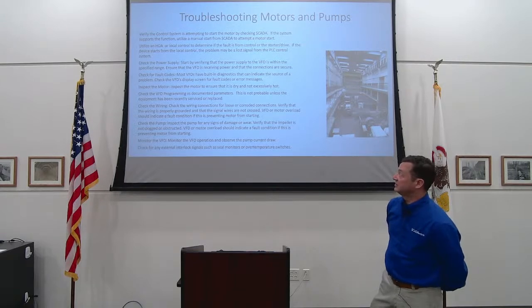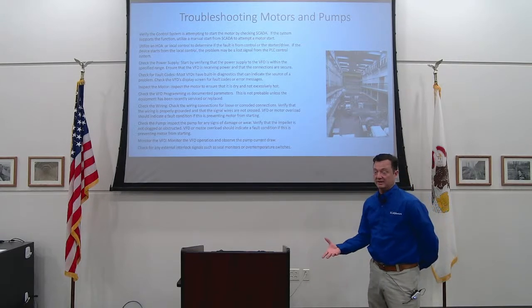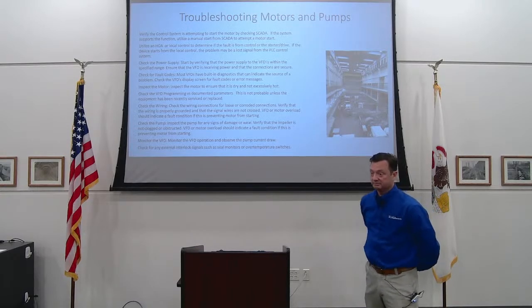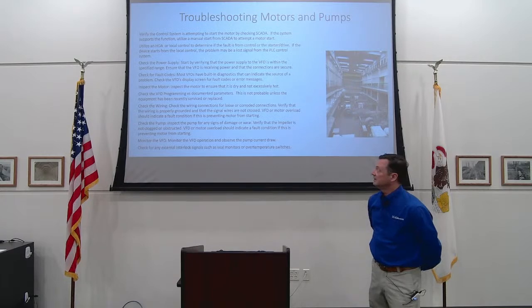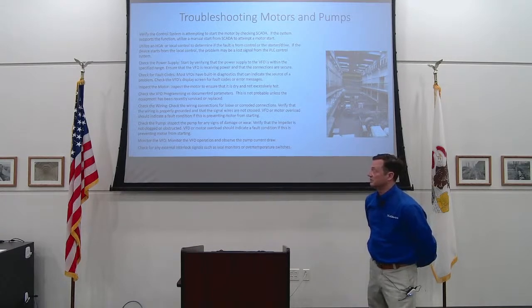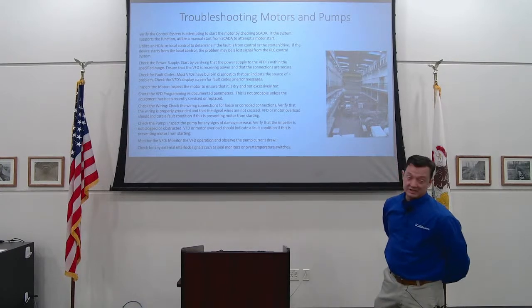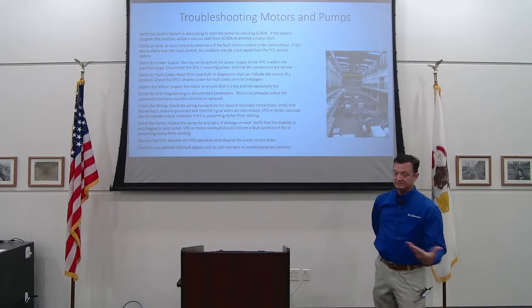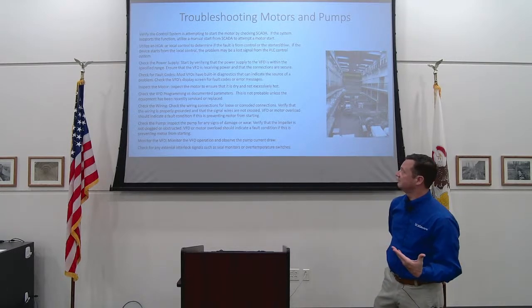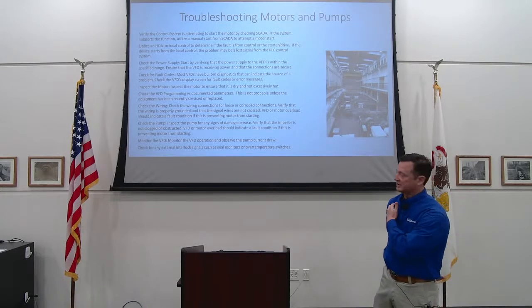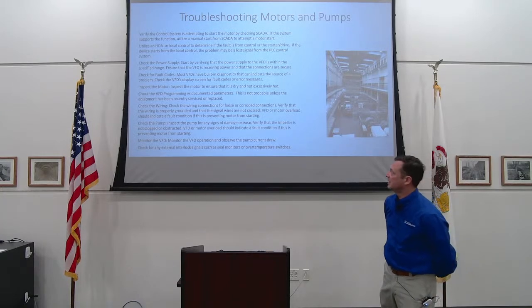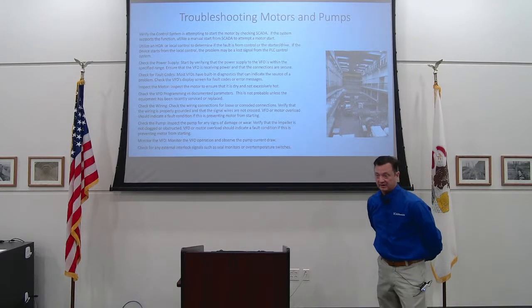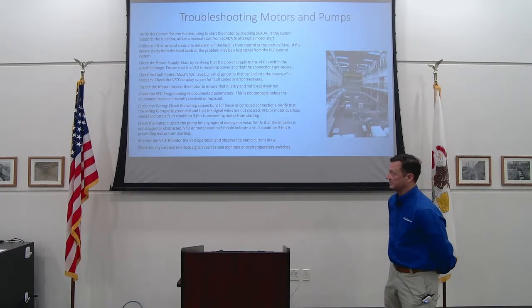Inspect the motor. Make sure the motor's dry. Make sure it's not excessively hot, right? The pump could be cavitating, and you could have a process problem that's causing the motor to trip out. If the VFD has been changed recently, then you go through and check parameters in the drives. That would be really not probable under normal operations unless something's recently been changed. Check wiring for any loose or corroded connections, and verify things are grounded properly. That's something I would expect an electrician normally to be doing. Obviously, an integrator could be doing that too, and just checking the pump for damage or wear.